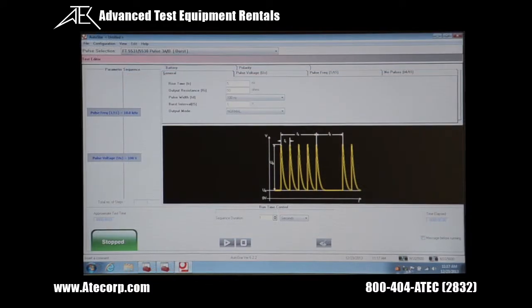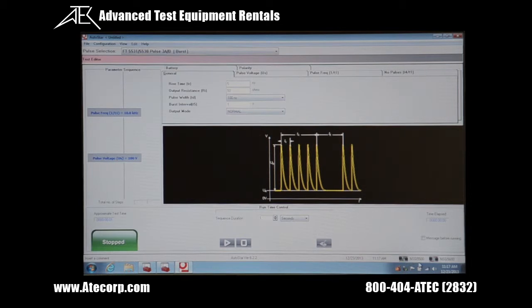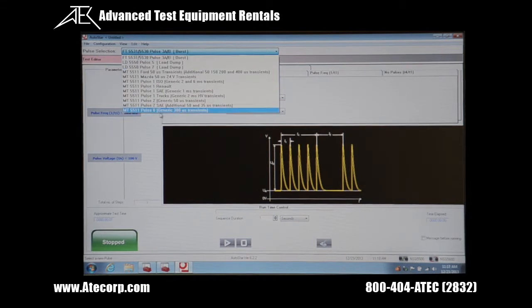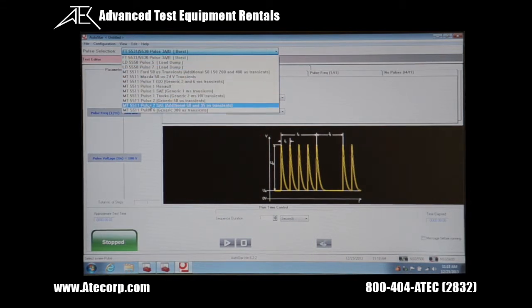You want to make sure you're actually connected. You can go down here and look, and you'll see the NSG 5500 has a green bar between the units, showing that you do have communications. The next thing you can do is go to this drop-down — it'll show you the main pulses that are available with the modules that are installed.